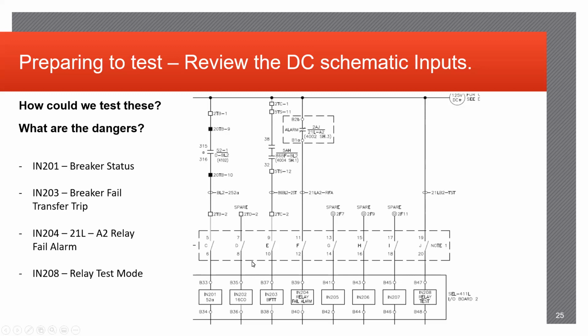Going into some of the other stuff, this breaker fail transfer trip. Again, this is associated with a breaker failure situation where a fault can occur in the site and pretty much need to isolate more than one piece of equipment to ensure protection to the in-service stuff. This will be done usually over a POTT or direct transfer trip if it's communication based, but in this case, it's actually just coming from a lockout.